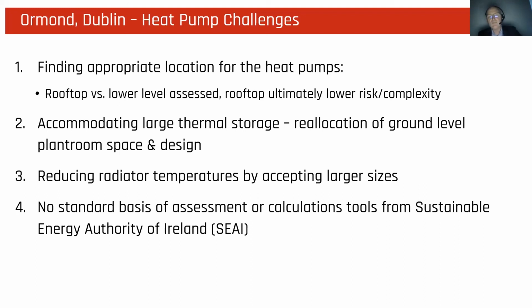Now, the reduced radiator temperatures did increase our radiators by 26% on Ormond, and that wasn't too bad. We put 2 radiators in the living space and 1 radiator in each of our bedrooms. Our apartments are quite well sized. They're 80 square meters for the 2 beds and 50 for the 1 beds. We have a nice high 2.75 ceiling, so there's good volume in the apartments.